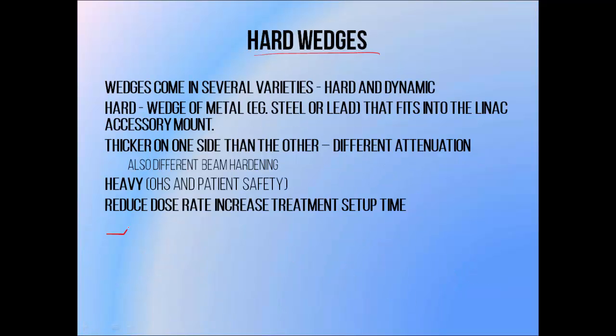The type of wedge filter I just described is called a hard wedge. It's a wedge-shaped lump of metal, so it's thicker on one side than the other. It can be placed on a linac accessory mount just below the window through which the beam exits the treatment head. It works by attenuating parts of the beam that pass through the thicker side more than those that pass through the thinner side.